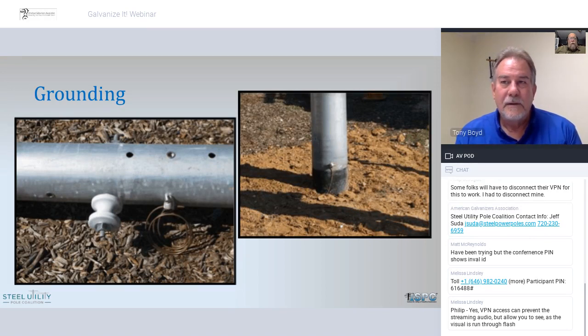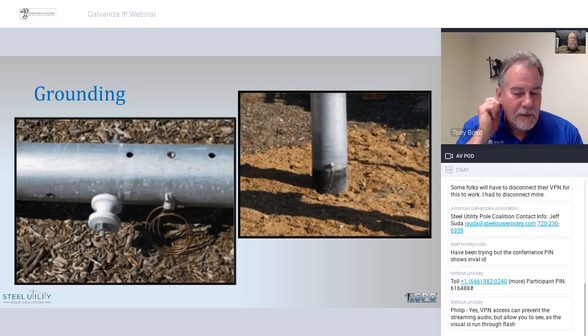So I think that the takeaway here that you should see is that OSHA's expectation is that it doesn't matter if it's wood or steel. They're all supposed to be considered as conductive. They're all supposed to have covers in place or insulation and isolation in place when we work energized at the top of a pole. And there is no validity to the argument on either side. So steel pole manufacturers, when you're looking to sell or promote your product into the industry, need to be aware that wood poles are not safer to work with than steel poles. And linemen and contractors and utilities on the construction and maintenance side need to understand that there should be, as far as they're concerned, no difference between the two.